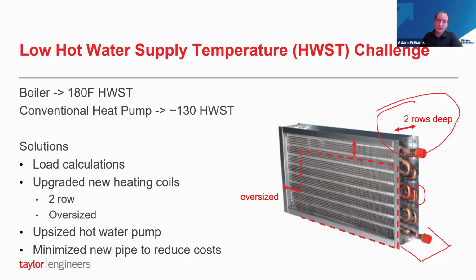So that's what we went with, was 2-row oversized coils to increase the heating coil capacity at the lower temperature. Next thing we did, we upsized our hot water pump. Again, what we found is that you can increase the flows through hot water systems by a little bit before you run into noise and erosion problems associated with increasing flows through existing hot water pipe. So we did all of that, and that significantly minimized the amount of new piping distribution that we had to change or add, basically, to make sure we didn't run into problems.